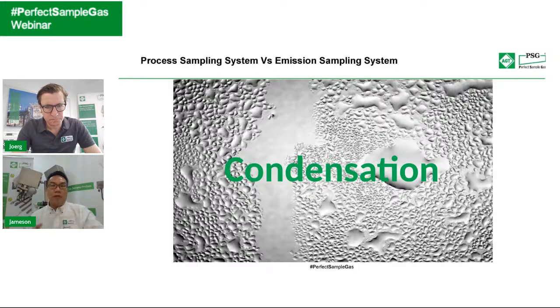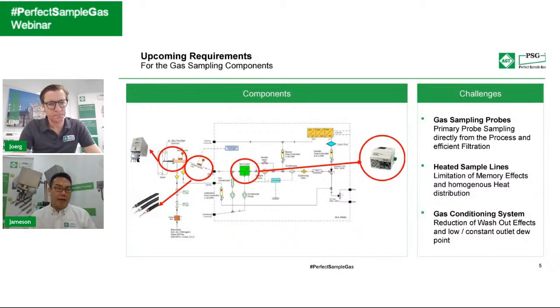So at the point of commissioning, let's say you have a 5 liter per minute pump, so you are sucking 5 liters per minute. And most of the analyzers, infrared analyzers, not all, but most of them, require a flow rate of 1 liter. But you have a 5 liter sample pump. Where is the 4 liters? So people think, okay, I can have a parallel needle valve, or I can have a bypass flow meter to regulate. Yes, nothing wrong. Question: are they regulating correctly?